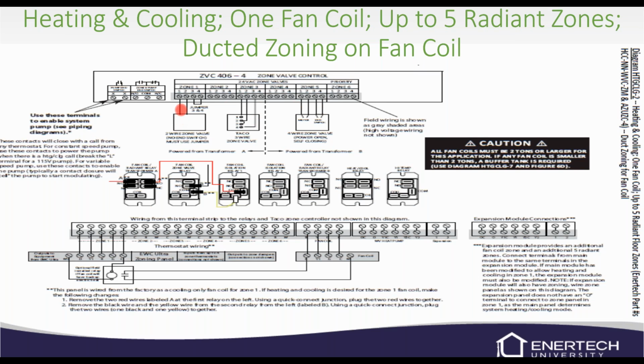And this is a ducted zoning on a fan coil, up to 5 radiant zones in one fan coil. All these gray areas in these wiring diagrams, that's field wiring. So anything here, this is all going to be field wiring here, and then up where your thermostats come in as well.